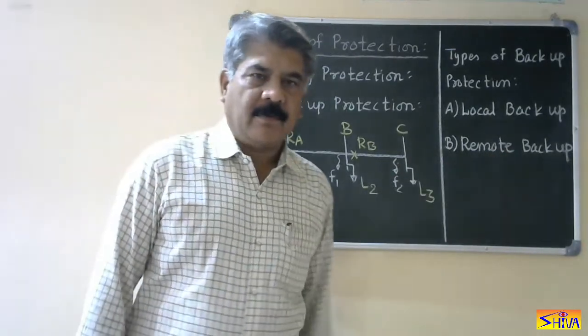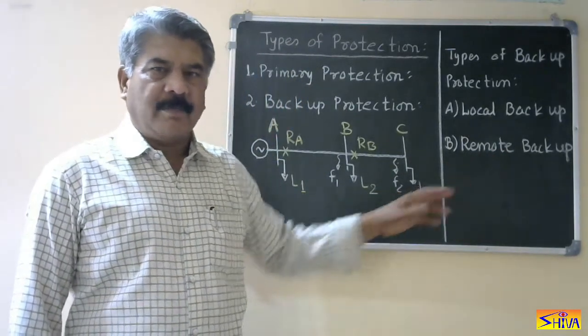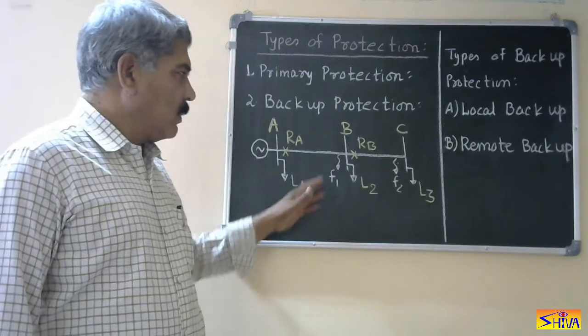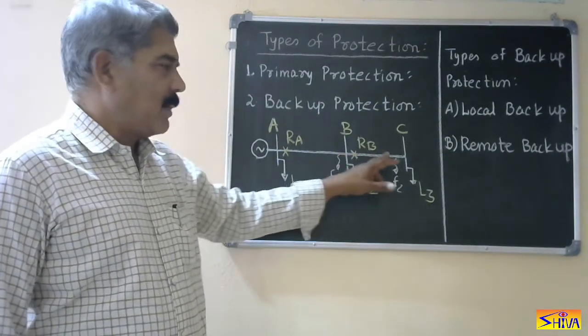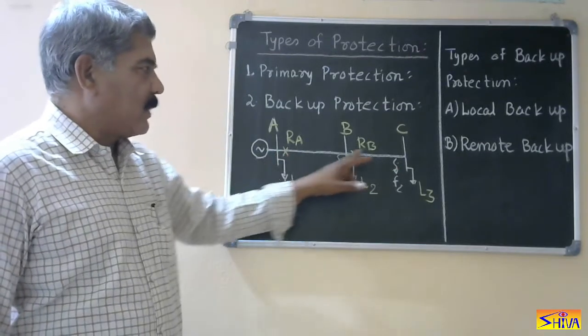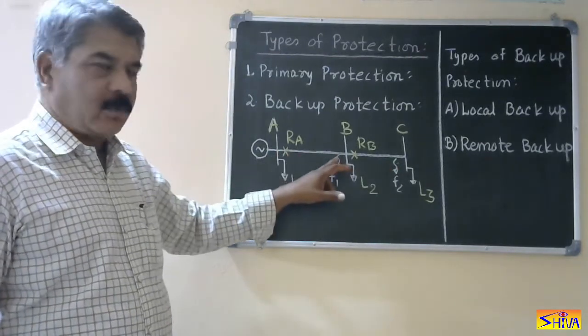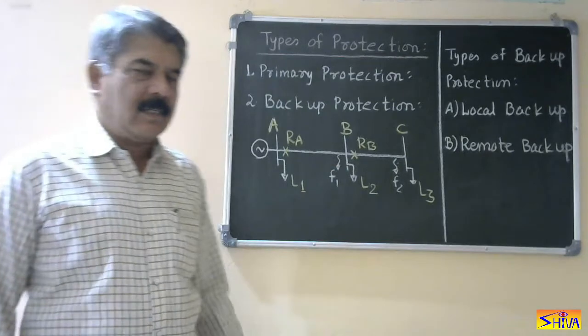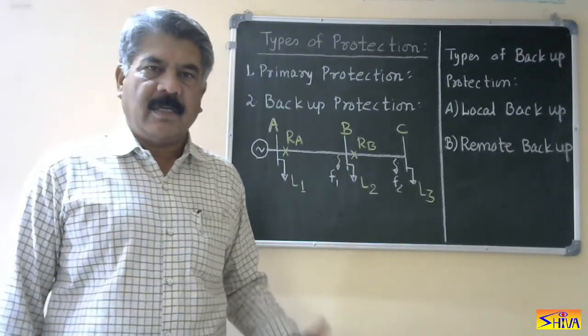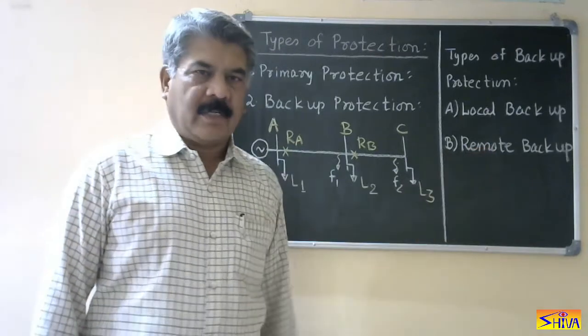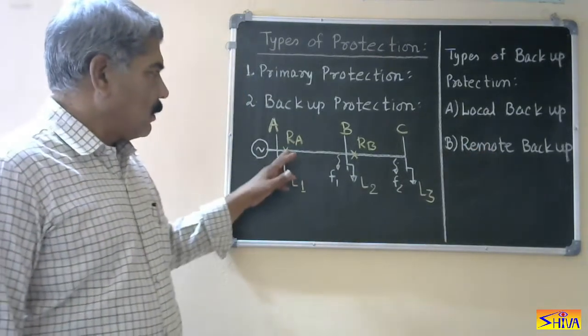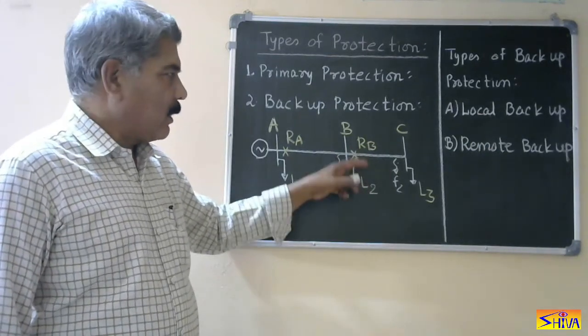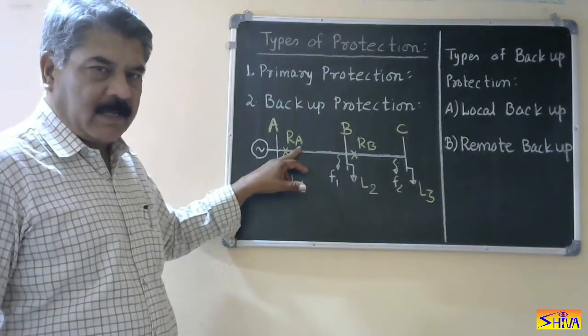The second type is remote backup protection. As the name indicates, it is not provided at the same location — it is provided somewhere else. In this case, R-B is acting as primary protection to section B-C, and R-A will act as backup protection to section B-C. R-A also acts as primary protection to section A-B and backup protection to section B-C. The advantage is that no additional cost is required to install the remote backup protection.